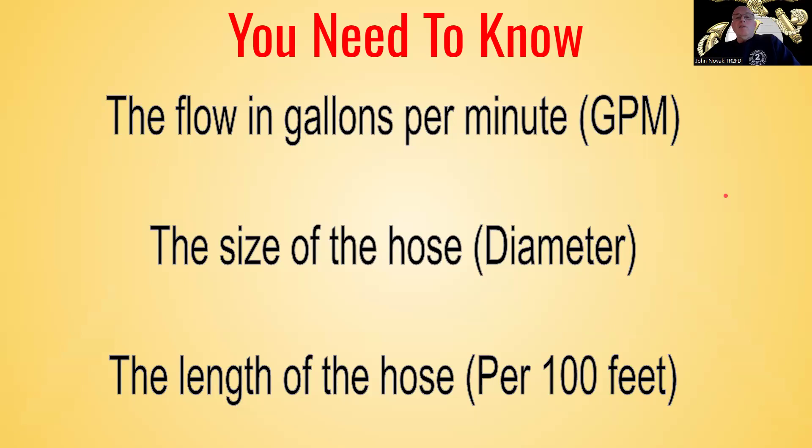We're going to need to know the size of the hose, so that would be the hose diameter. We're dealing with inch and three-quarter hose and two and a half inch hose for this video. We're going to need to know the length of the hose per hundred feet. We base our friction loss for every 100 feet of hose.